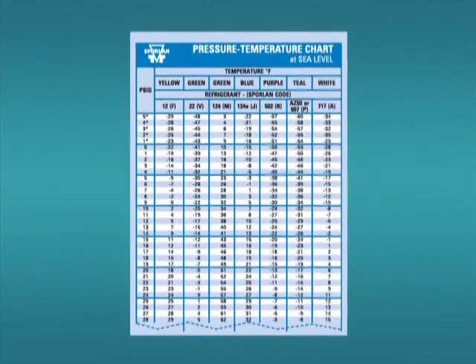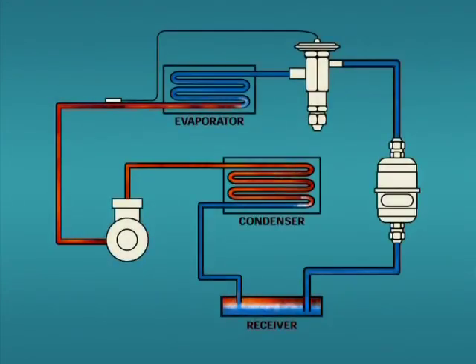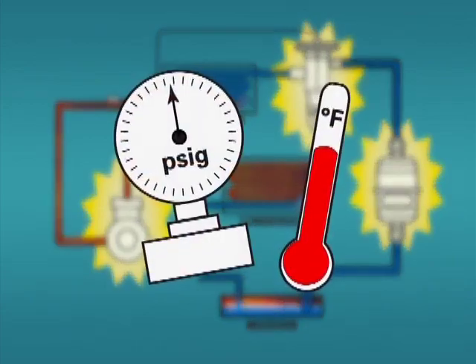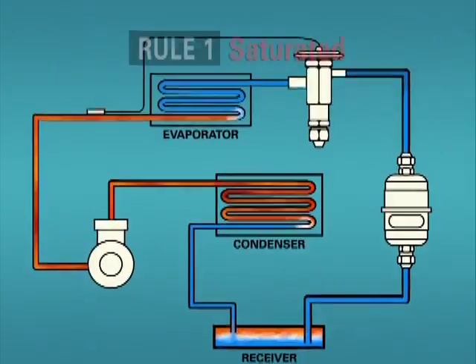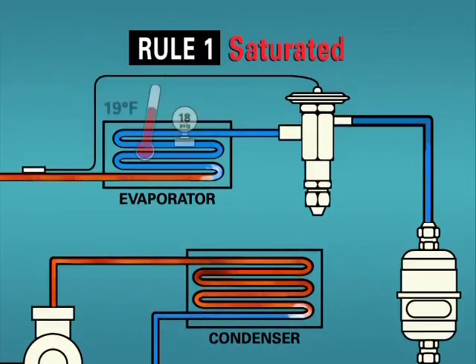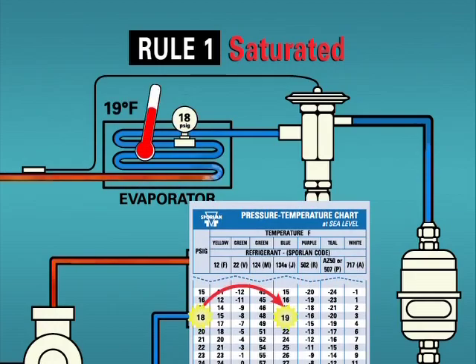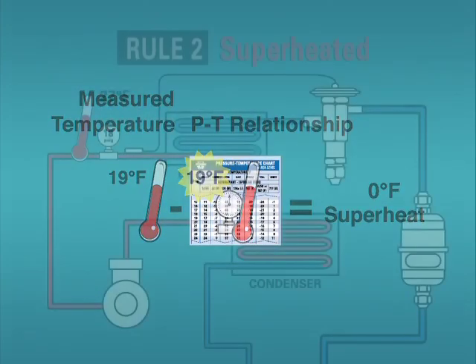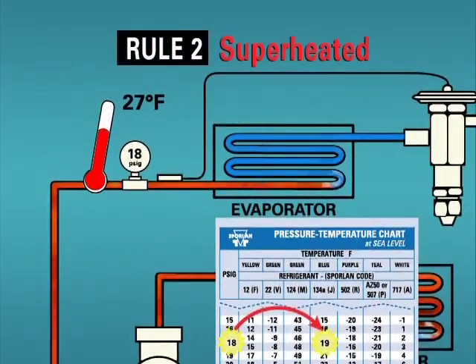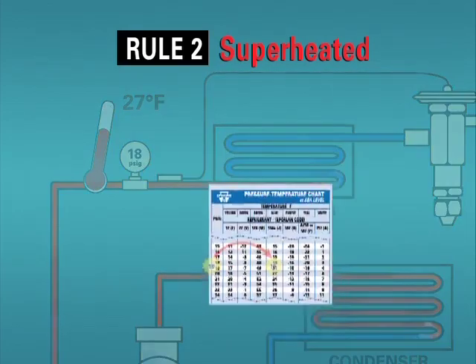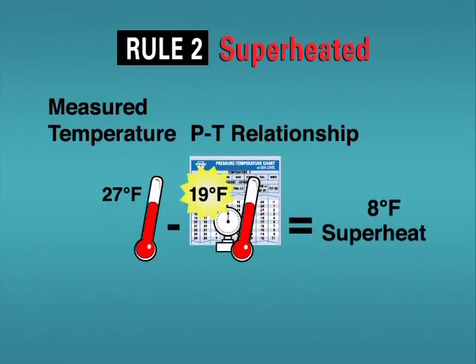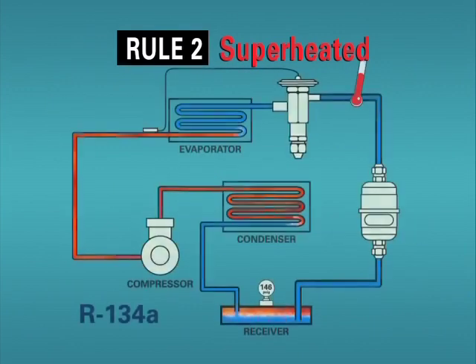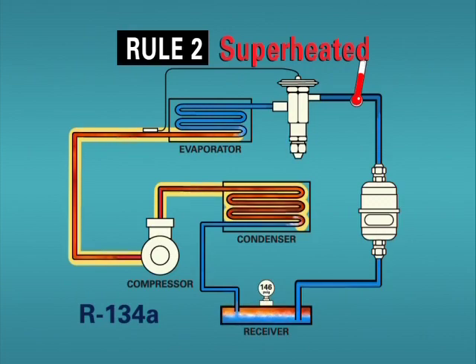With the PT card, we should be able to determine the condition of the refrigerant at any point in the system by remembering the following rules. Rule 1: If we have a liquid and vapor mixture present, as we do in the evaporator and condenser, we have saturated refrigerant which will correspond to our PT card. Rule 2: We have superheated vapor when our measured temperature is greater than the saturation temperature indicated by our PT card. The amount of superheat will be the difference in these two temperatures. Superheated vapor will be present in the suction and discharge lines of a normally operating system.